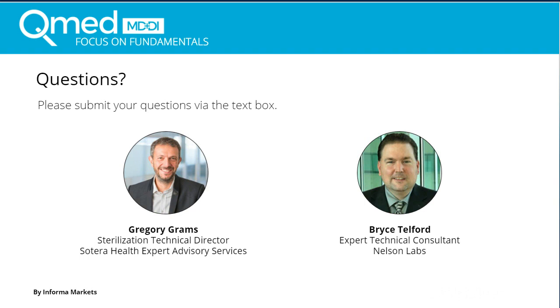Yeah, that's a really good question, because currently the ISO 10993-7 is not giving you any guidance on how many samples you would need, and also not where to place these samples, because we have to be cognizant of the fact that if we have samples on top of the loads, they will be outgassing faster than the ones in the center of the load.